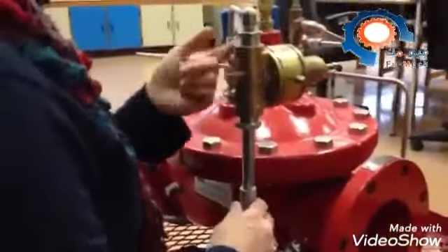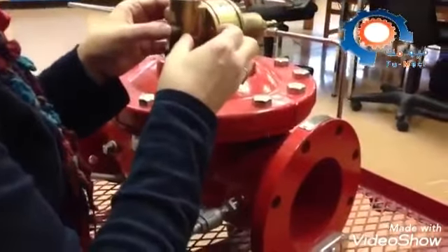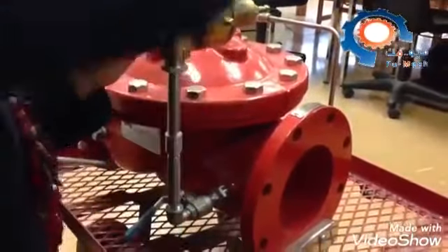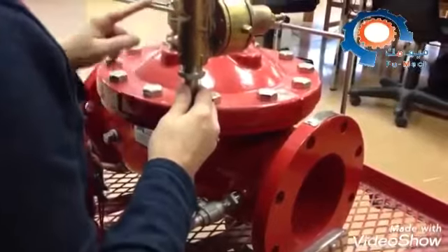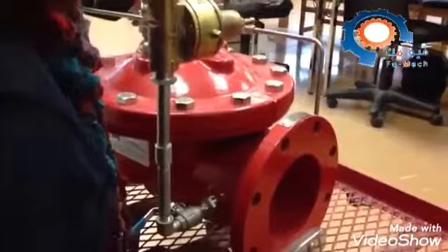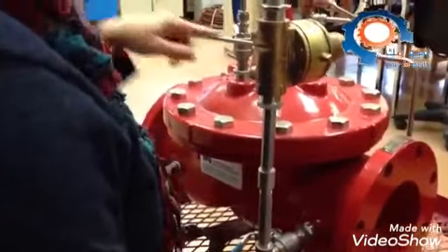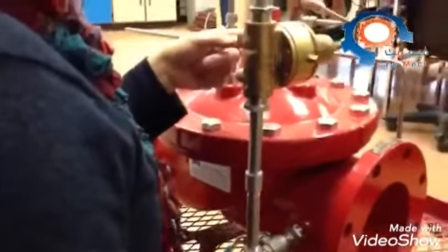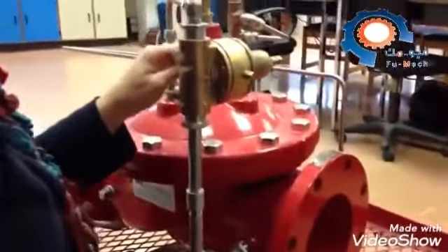And it's got two completely separate chambers. It's got the valve body chamber, which is here, which allows water to pass through onto the top of the bonnet. And the other thing that it's got going on here is a sensing chamber that senses the downstream pressure. And if it goes above 80, what's going to happen here is it starts to close that valve. Well, it starts to close it, but how does it start to close it?